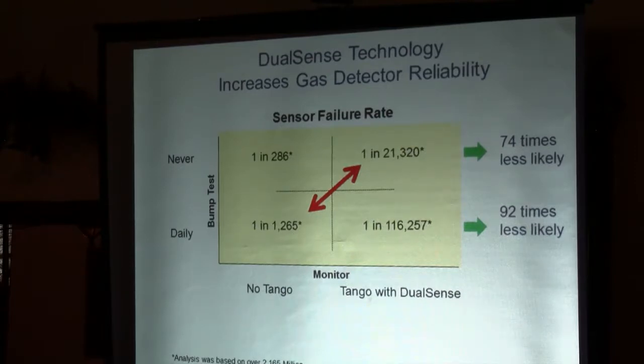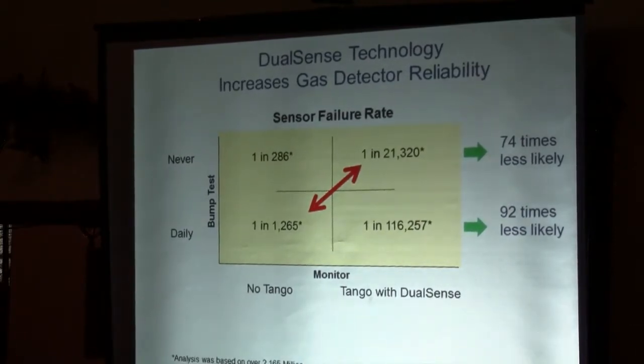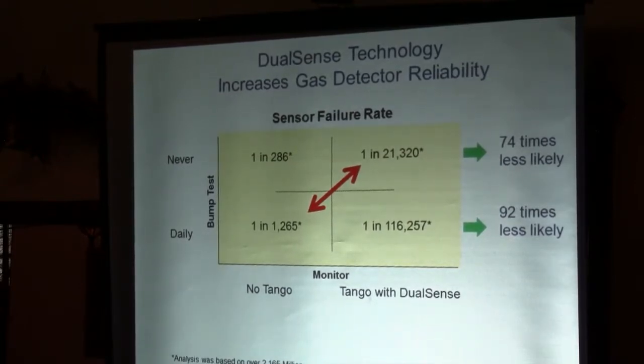A normal single gas device has a failure rate of 1 in 1,200 instruments. You employ DualSense, failure rate's 1 in 21,000 instruments. That lets us be a lot more cost-effective device for you than buying a cheap throwaway device. This is also fully serviceable, so you could put sensors and batteries in this for as long as we offer them.